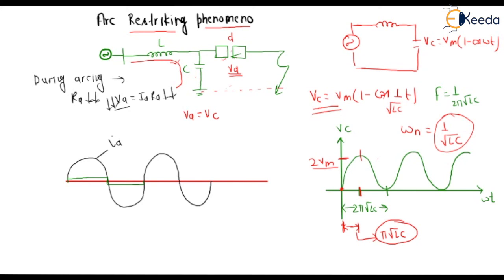So I'm repeating from the start. The primary arc will initiate, and when we quench this, this will be an open circuit, and the oscillating voltage across the capacitor will appear across the contacts of the circuit breaker, having a maximum value of 2 Vm. And once again the checking will be done, and when the dielectric stress is greater than the dielectric strength of the material, then the arc will restrike. That is why this phenomenon is called arc restriking phenomenon.